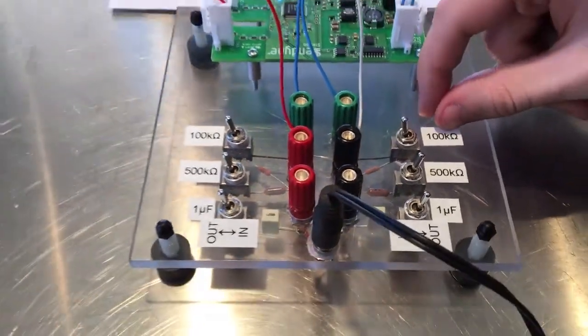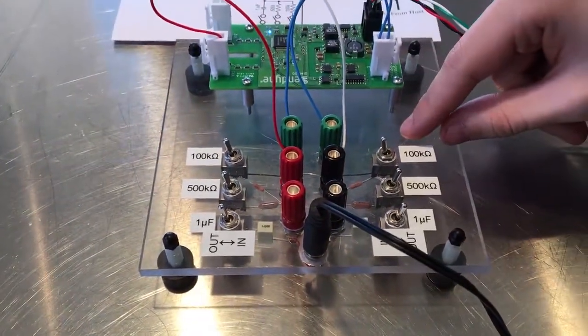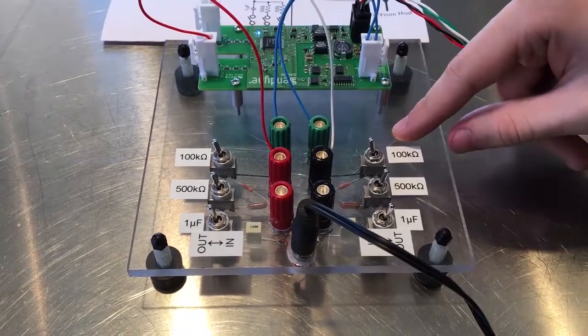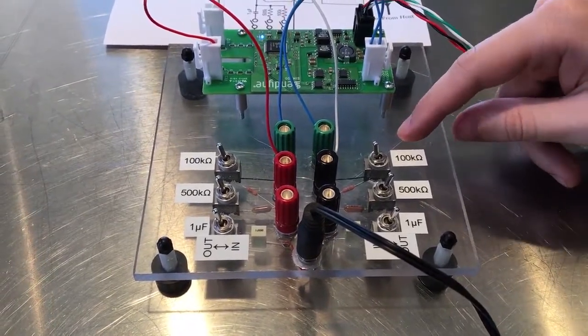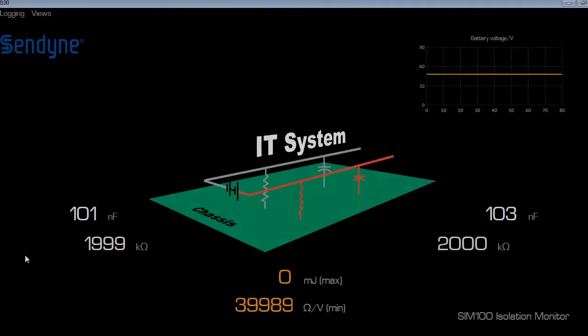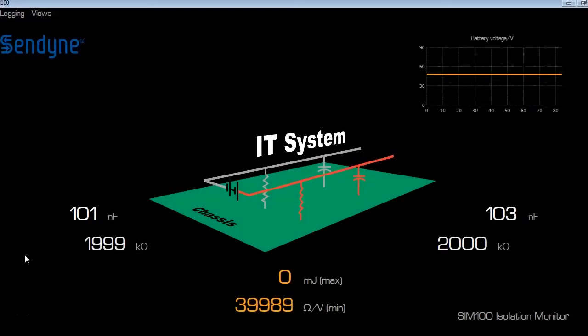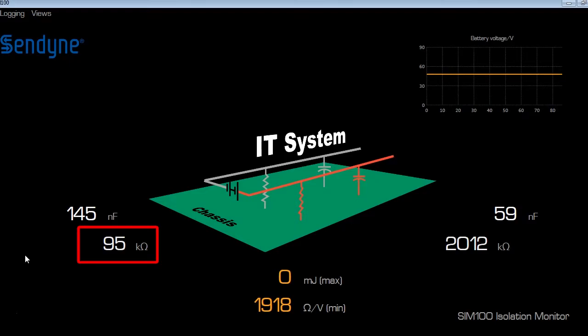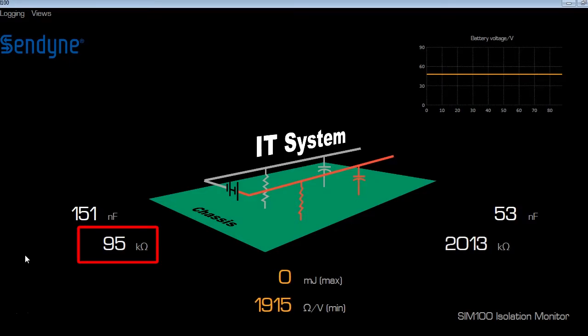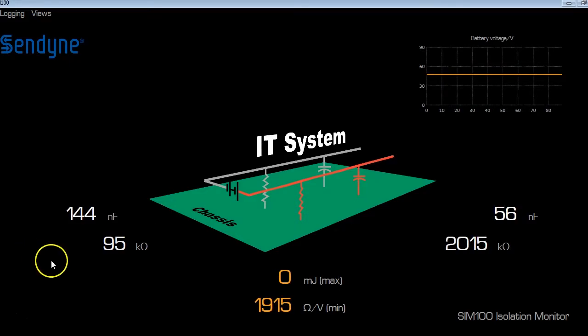Now that it's been added to the circuit, we wait for the SIM100 module to recognize the change. Once it does recognize the change, then it should say roughly 95 kiloohms of leakage resistance for the negative side of the battery.